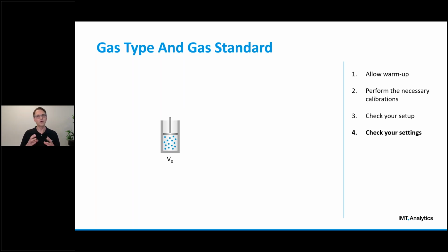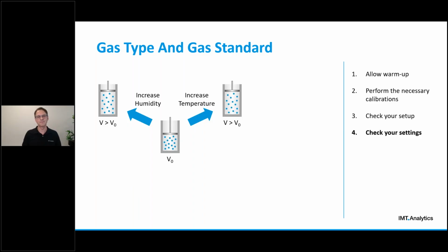The reason is that the volume occupied by gas is dependent on several different factors. So let's assume here on this slide you see a container, and let's assume we can capture some room air in that container with a movable lid, and let's call that V0 for volume 0. What happens if we increase the temperature of that volume of air? The answer is it's going to expand and occupy a greater volume. The same applies when we increase the humidity of the gas.